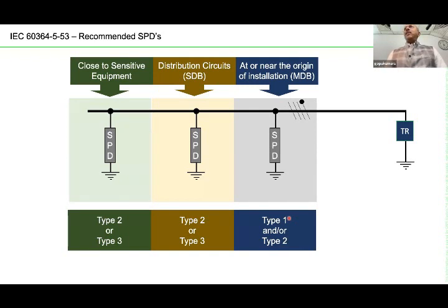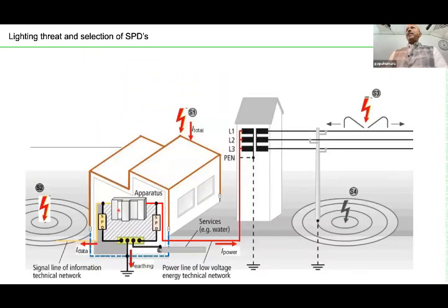That applies where, for example, you don't have any lightning activity nearby, there is no lightning strike on your building, or you don't have any lightning protection for your building. In that case, you don't need to put a type 1 SPD. Or if your incoming power cables are all underground cable, the chance of lightning hitting the line and taking the energy through the line is less. Under that condition, you don't need to go for a type 1 SPD, you can go for a type 2 SPD. All these conditions are included in the standard. Similarly, in the sub-distribution board, you can go for type 2 or type 3 SPD. Near the equipment, again, type 2 or type 3 SPD. As I said, all this depends on the type of building, size of building, and the type of electrical installation and so on.